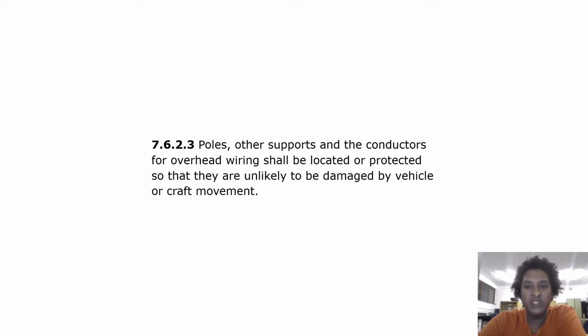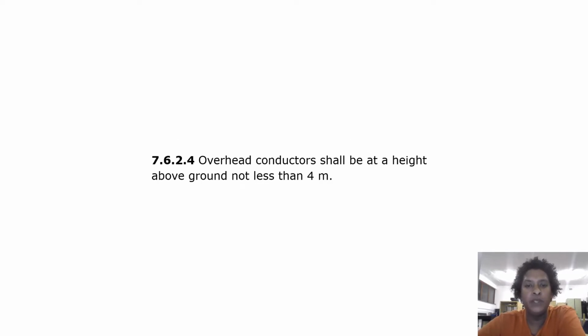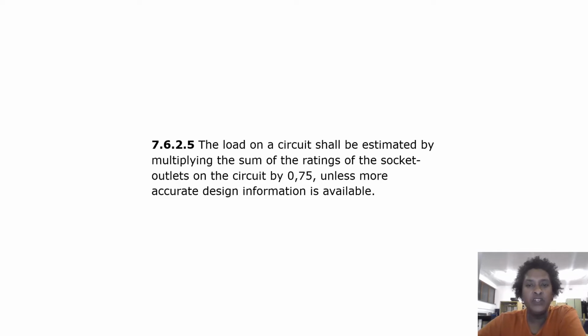Poles, other supports and the conductors for overhead wiring shall be located or protected so that they are unlikely to be damaged by vehicle or craft movement. Overhead conductors shall be at a height above ground not less than 4 meters. The load on a circuit shall be estimated by multiplying the sum of the rating of socket outlets on the circuit by 0.75 unless more accurate design information is available.